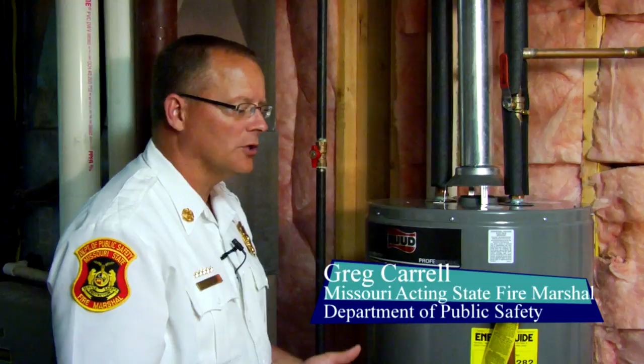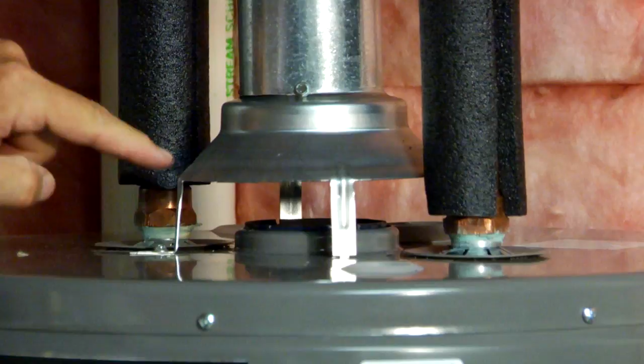Some of the things you want to look at from a maintenance standpoint with your water heater: you look along the vent pipe. If you find soot along the edge of this vent pipe where the flue is coming in, you probably have a problem with air coming back down, pushing the flue gases out into the room, and that can create carbon monoxide.